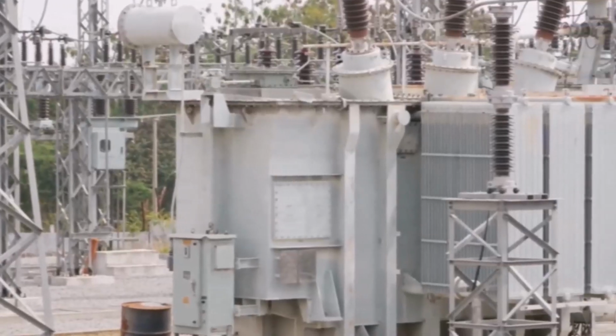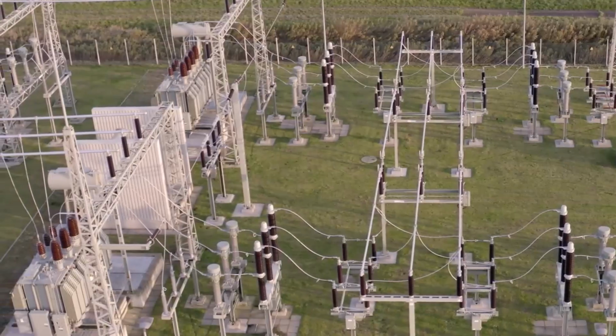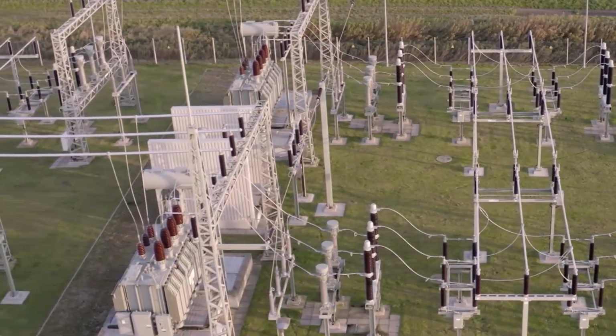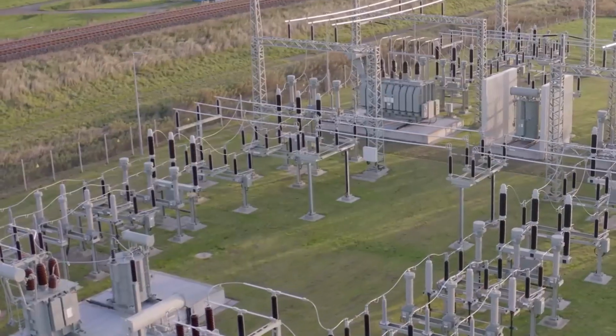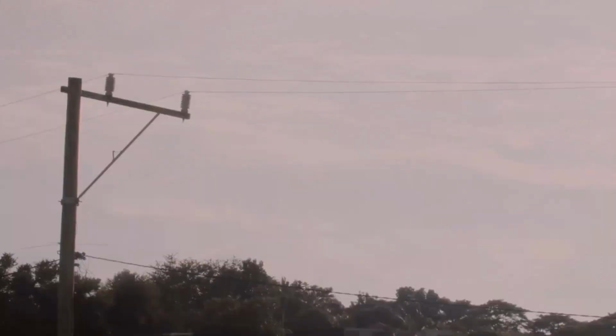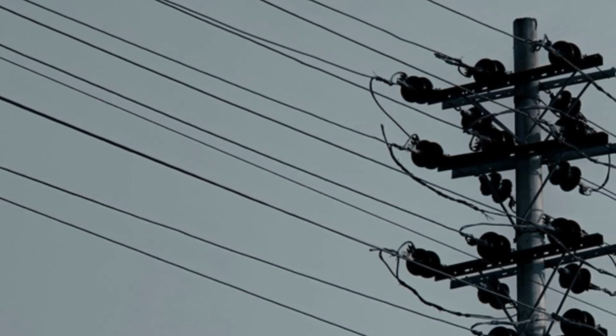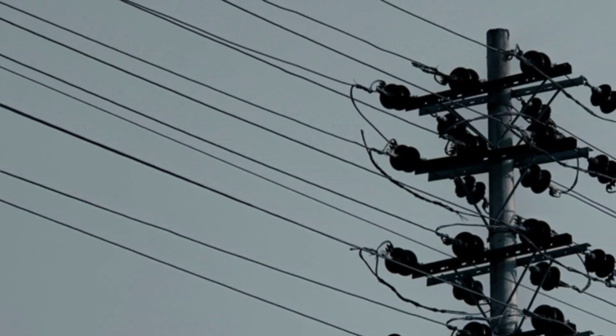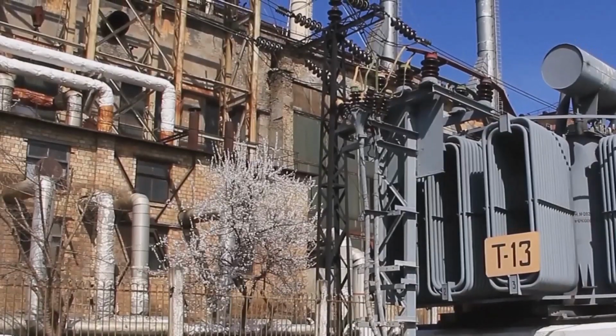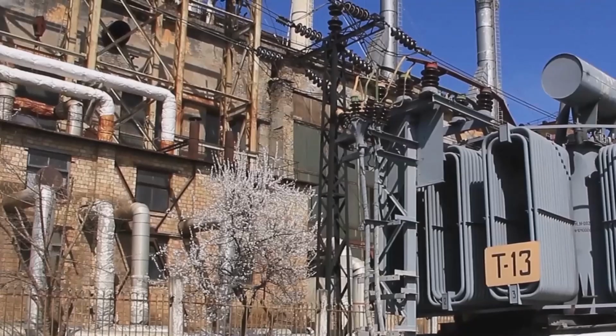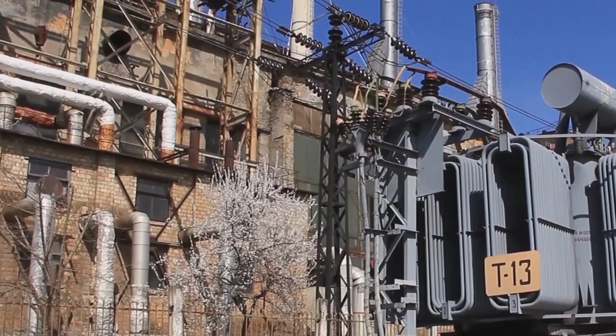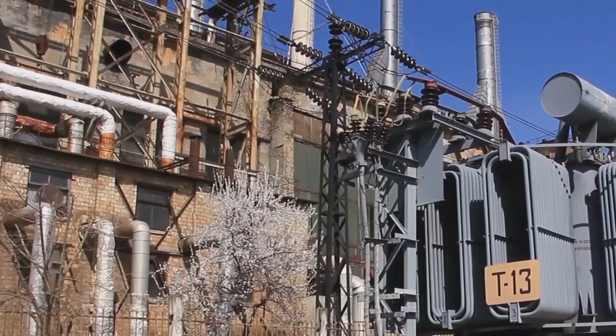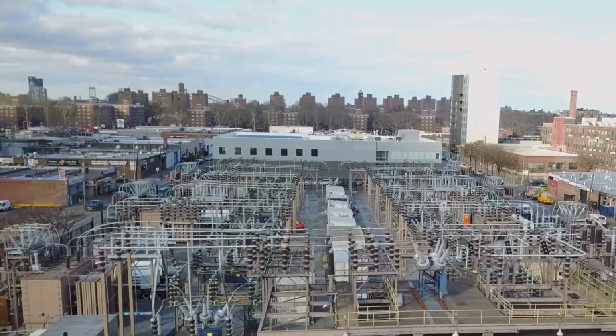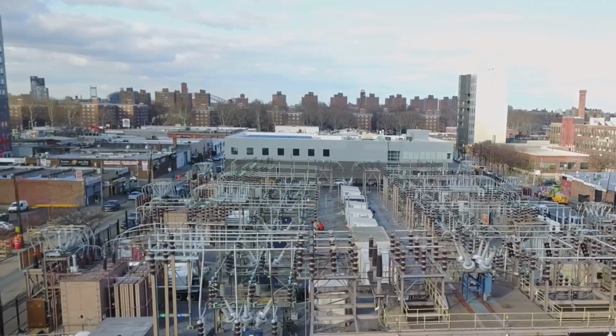Section 4. Y in the wild, real-world applications. If you want to see a Y connection in action, you don't have to look far. Just step outside and look up at the utility poles that line our streets. The power distribution systems that bring electricity to our neighborhoods almost always use a 4-wire Y connection. You'll typically see 3 main power lines running along the top of the pole and a 4th lower neutral wire. This setup allows the utility company to deliver high-voltage power efficiently over distances, and then easily tap into it to provide the single-phase power that our homes use. It's the standard for residential and commercial power distribution because of its safety and flexibility.